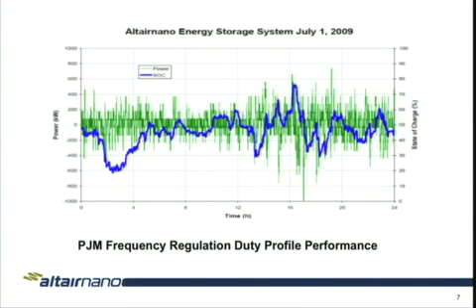So just quickly looking at this one here, through that 24 hours, we were using minus 400 to 400 kilowatts throughout the day. State of charge, once again, this is a 250 kilowatt hour machine providing this power up and down. In the afternoon, maybe some higher pulses, having to absorb power very quickly down to a megawatt. And the state of charge is relatively limited to the band of really 60 to 30 state of charge, so well within the 250 kilowatt hours of energy.